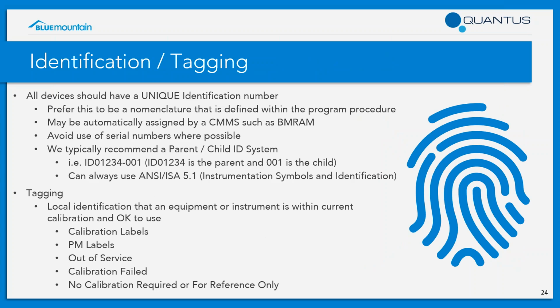Thank you, Chris. So we were going to mention identification and tagging, and this is an area where things can get really wild. I've seen all types of ID nomenclature, from smart identifications that tell you where the facility is located, the parent system it's on, the device ID of the instrument, and then a control number. I've seen device-specific identification numbers such as scale number 1 or pipette number 57, or more simply, just a unique, non-related sequential number that comes out of a CMMS database. The only thing we're typically not going to recommend using is the instrument serial number.